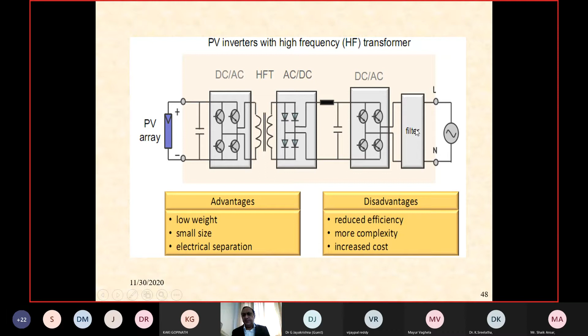The advantages are low weight, small size, and electrical separation. Disadvantages: reduced efficiency, more complexity, and increased cost. Reduced efficiency because of the two inverters and the high frequency transformer. More complexity because too many semiconductors are in place, and increased cost obviously for the same reason. PV inverters without a transformer are called transformerless.